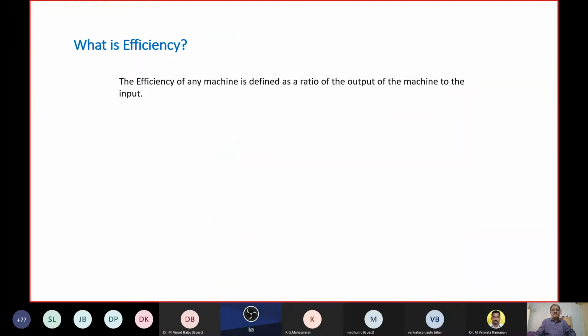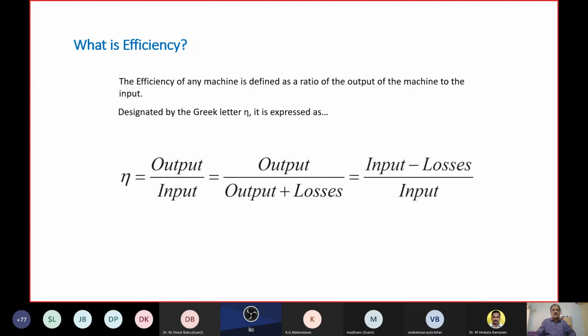So what is efficiency? I'm sorry if I'm sounding a little elementary, but many of us need an understanding of this. So efficiency is a percentage expressed as output divided by input. Or in other words, output divided by output plus losses. Or still, it will be input minus losses divided by input will be the efficiency. We can measure the input power to the motor through a power analyzer. Quite easy to deal with inputs on both denominator and numerator. Therefore, what would make the difference is the losses. So in order to achieve energy efficiency in a motor, higher efficiency in a motor, the losses must be reduced. This has to be understood.